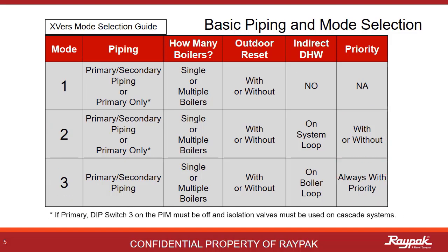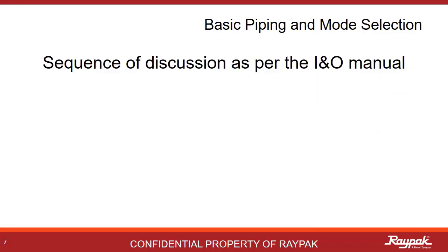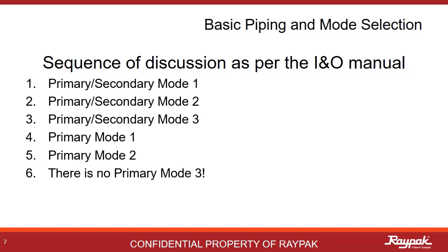An important note: if you are setting up a primary system with more than one boiler, PIM dip switch number 3 is off and the isolation valves must be used. When you commission a new XVers-controlled boiler, you set the mode selection in the adjustment section of the operations menu. The installation and operation manual covers the mode selections in this order, so this presentation will mirror that sequence — first the primary-secondary modes, then the primary modes.